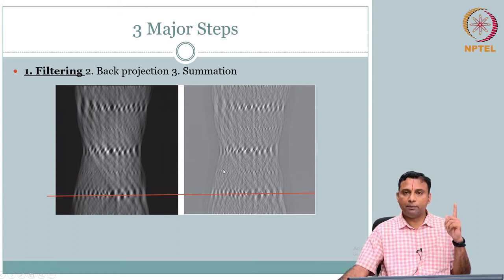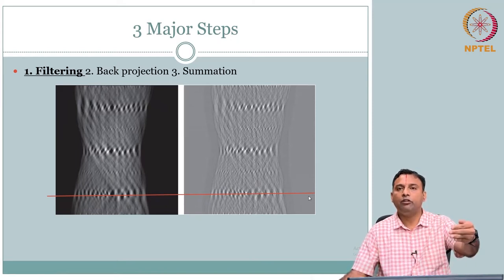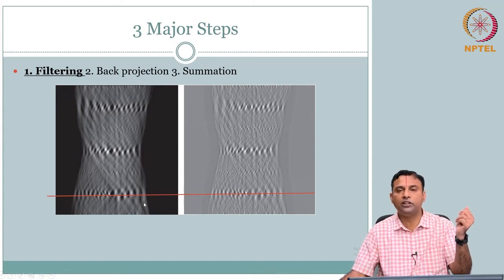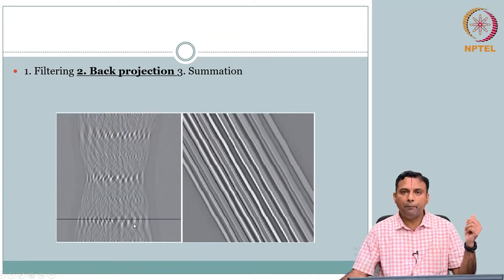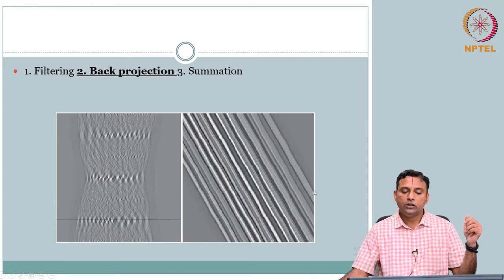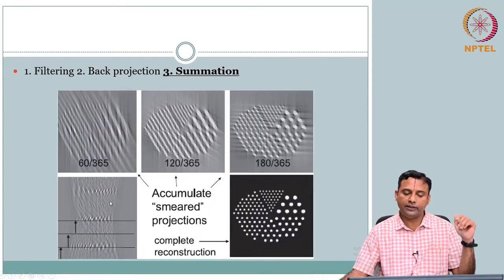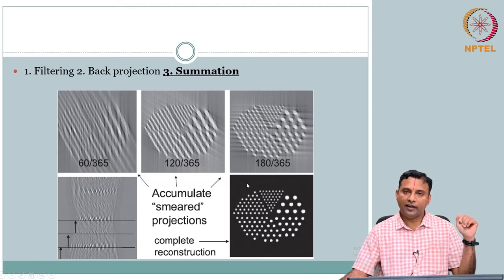This is a filtered version. The second step: for each view angle, you have a projection — now filtered — and you have to back project it in the field of view along the orientation in which it was acquired. We took a particular angle, say theta=30 degrees as an example. You take the projection along that line and project it back along the field of view at that angle. This is your back projection — same as before, but now starting with filtered projections. Then finally, summation. Each back projection image itself is lousy, but when you start to add them — the more you add — you get the final reconstructed image.